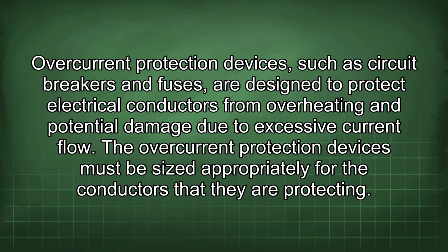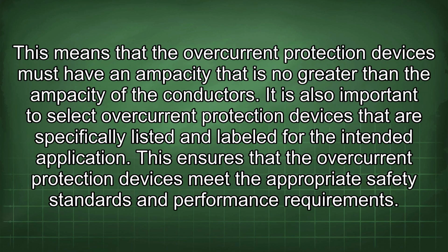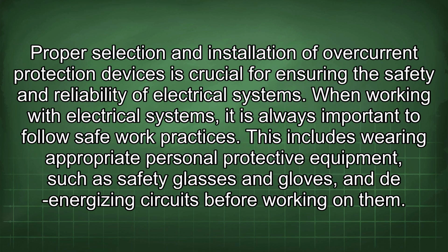Overcurrent protection devices, such as circuit breakers and fuses, are designed to protect electrical conductors from overheating and potential damage due to excessive current flow. The overcurrent protection devices must be sized appropriately for the conductors that they are protecting. This means that the overcurrent protection devices must have an ampacity that is no greater than the ampacity of the conductors. It is also important to select overcurrent protection devices that are specifically listed and labeled for the intended application. This ensures that the overcurrent protection devices meet the appropriate safety standards and performance requirements. Proper selection and installation of overcurrent protection devices is crucial for ensuring the safety and reliability of electrical systems.